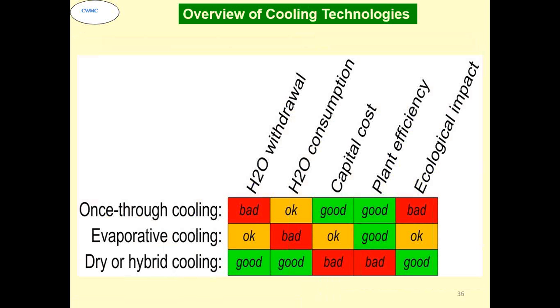If we compare the systems: in the once-through cooling system, water withdrawal wise it is bad, water consumption wise it is okay, capital cost is okay, plant efficiency is good, but ecological impact is bad, because the temperature of the water going to the water body is generally higher than the input water. Evaporative cooling, water withdrawal wise it is okay, consumption wise it is bad, capital cost is okay, plant efficiency is okay, ecologically also it is okay. Dry or hybrid cooling, water withdrawal wise it is good, consumption wise also good, capital cost is high, plant efficiency is low, and ecologically it is good.